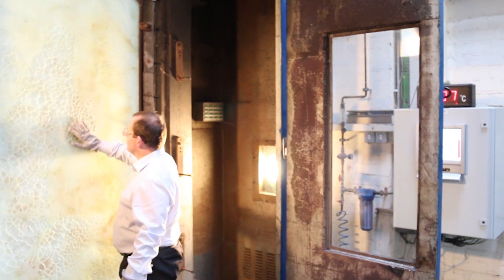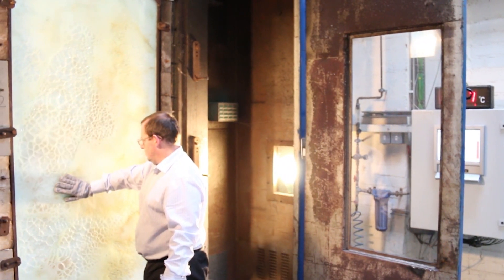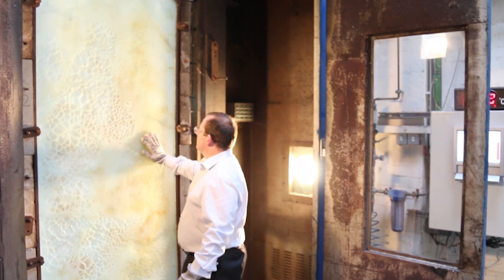But that is only half the story. We have to protect from the 1100 degrees, but also what we have to do is protect on the non-fire side. And here we have to contain the temperature to an average of less than 160 degrees. You could actually put your hand within 20 centimeters of that glass and feel no discomfort at all.